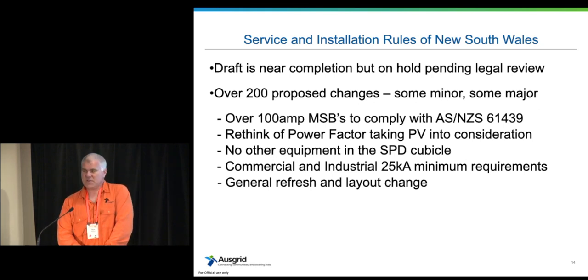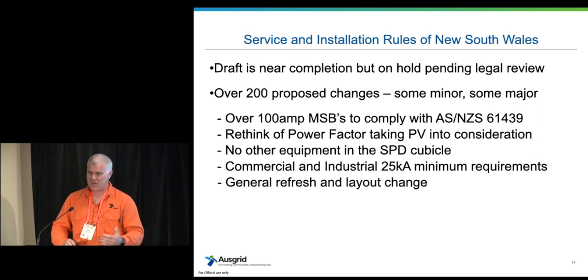And no other equipment in the SPD cubicle. So the issue there is not only is it something that needs to be sealed because it's unmetered, and we've got Ausgrid or the DNSPs will want to see the settings for the discrimination set and sealed. There's the other issue there of working live. So not only is there the issue that we, as a DNSP, have with security for our network and being able to wind up those protective devices, if you're opening up that SPD cubicle, you'll find yourselves in strife pretty quickly with safe work, because you're now working live in that cubicle. So that's something else to think of.